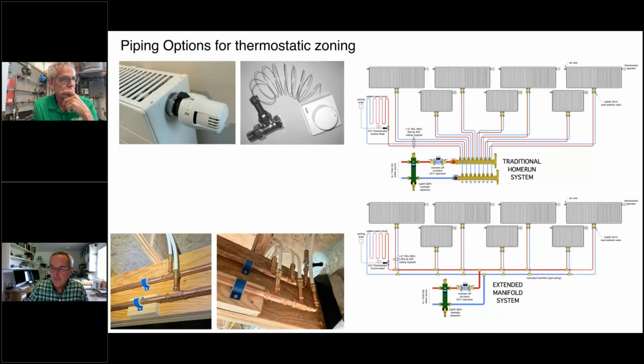And you see we've got 1/2-inch PEX going out to each radiator. Each radiator's got a TRV on it. Each radiator's got a dual isolation valve. Then on this end, I purposely threw in a radiant panel circuit. It could be floor heating, wall heating, ceiling heating. And that's where we use this assembly right here.